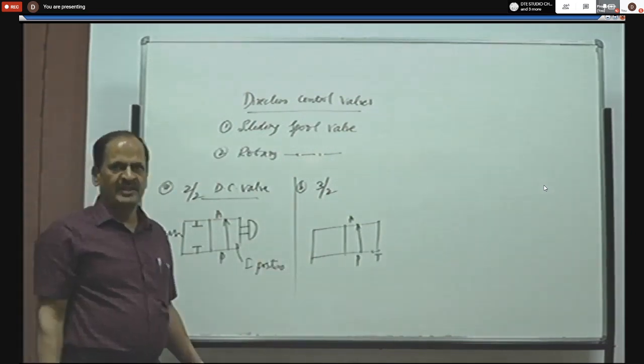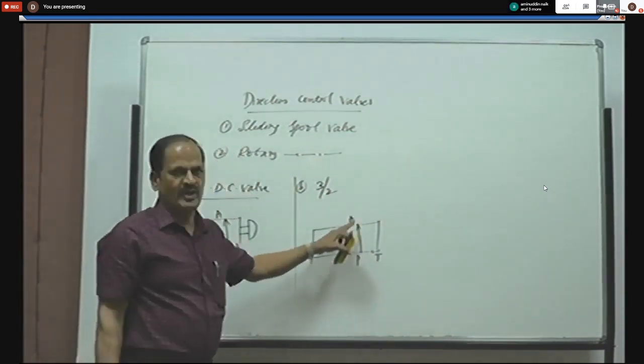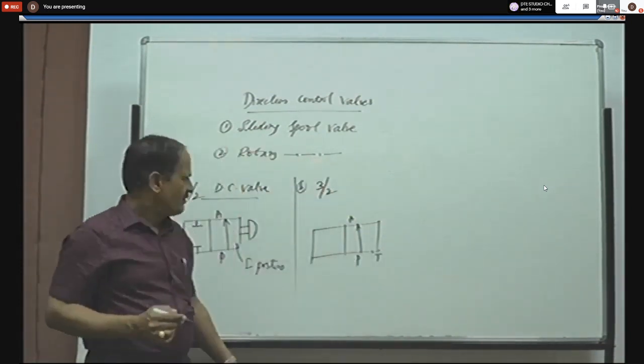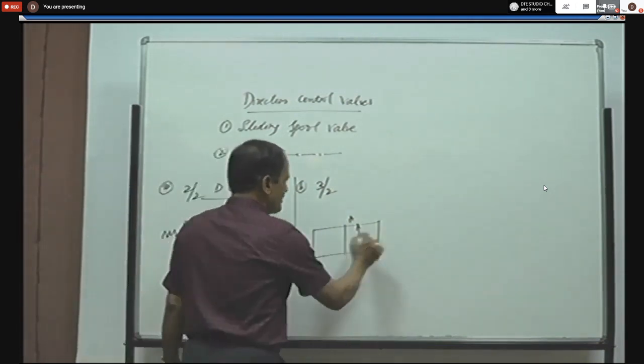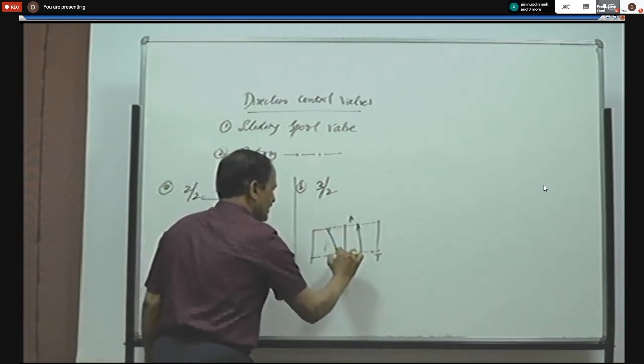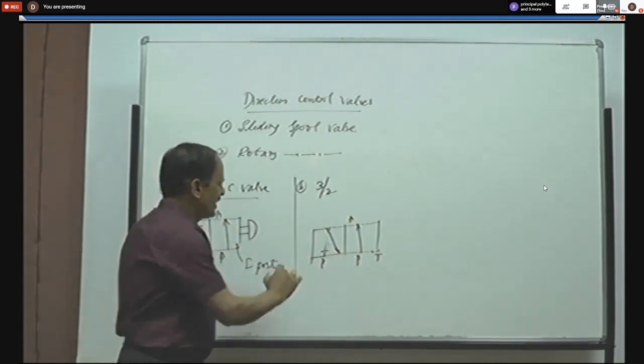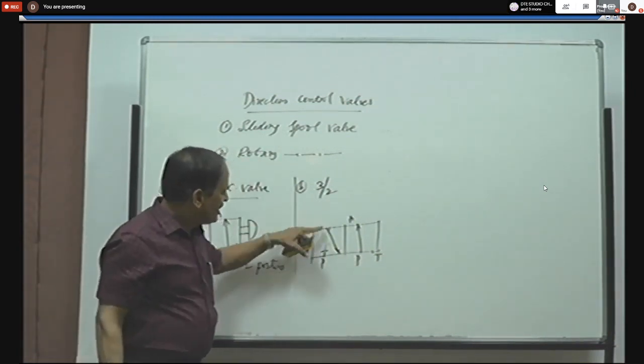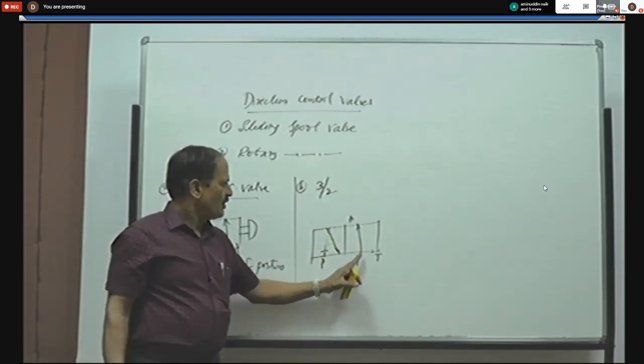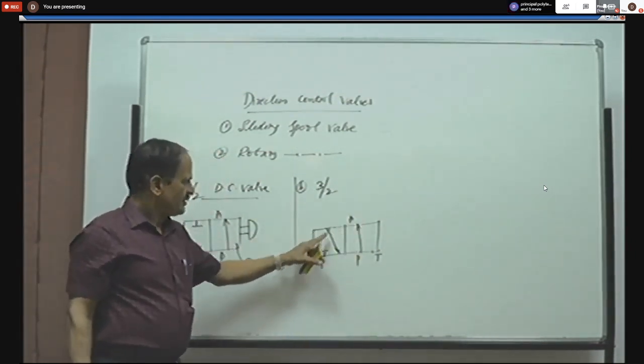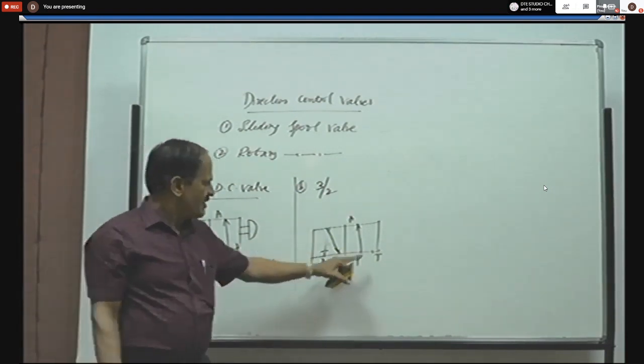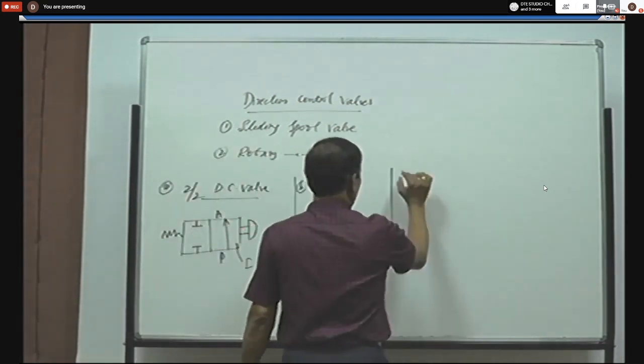In the case of 3x2, there are two positions and three ports. In the first position, ports P and A are open and fluid flows from P to A. T is the exhaust port, which is closed in the first position. Whenever the push button is released, A is connected to T and P is closed in the second position — direction of flow is from actuator to the tank reservoir. So fluid flows from P to A in the first position, and in the second position fluid is returned back to the reservoir from A to T and P is closed.